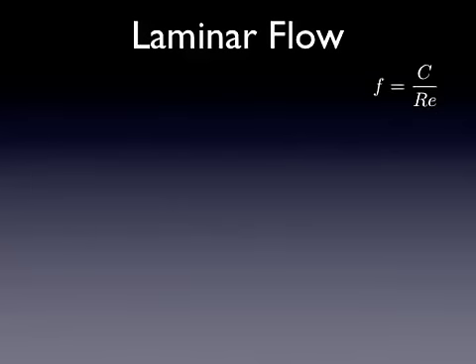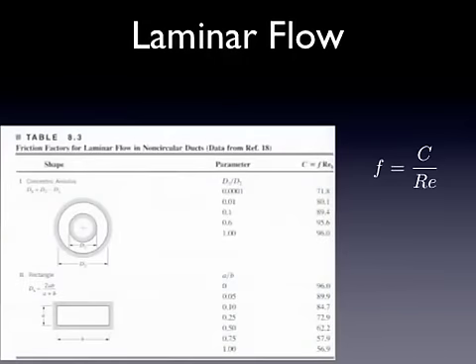In laminar flow, we talked about the friction factor being exactly equal to 64 over the Reynolds number. Remember we don't have to use the Moody diagram. We can just use this equation directly. That 64 is specific for a circular pipe.